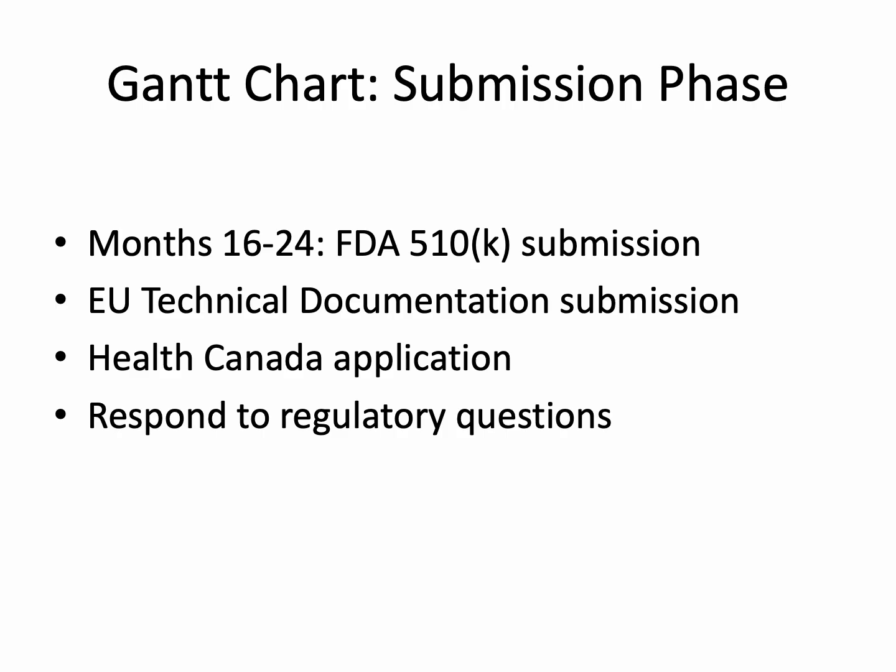The submission phase involves formal applications to regulatory authorities. FDA 510(k) submissions undergo a 3 to 6 month review. EU MDR technical documentation is assessed by a notified body over 6 to 9 months, and Health Canada applications are reviewed within 4 to 7 months. Timely and thorough responses to regulatory queries are critical for maintaining review timelines and achieving approval. Coordinated submissions across jurisdictions allow leveraging of clinical and technical evidence to optimize efficiency and reduce redundant work.